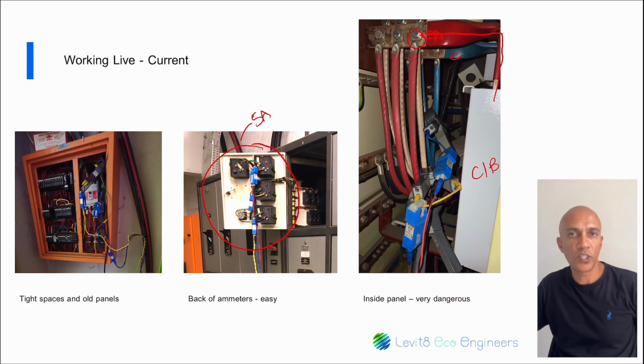So let's assume that you have a CT ratio of 500 to 5 and your load is at 100 amp. So your secondary amps will be 1 amp and the transducer will give you 1/5 of 1 volt, which will be 0.2 volts. The instrument will then display 1 amp, or if the CT ratio is set in the instrument, it will display the actual 100 amps.